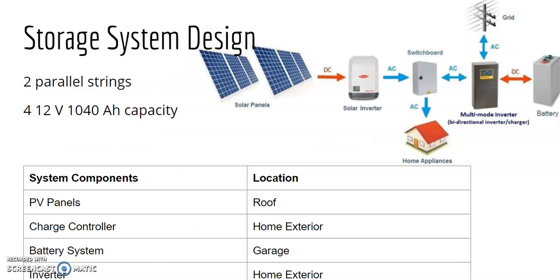For the system design, the storage system will consist of 2 strings of batteries, each string consisting of 4 12-volt 1040 amp-hour capacity batteries. Each component, as well as its location, is depicted on the table below. PV panels will be located on the roof, while the charge controller and inverter will be on the exterior of the home near the utility meter, and the storage system will be located in the garage. Our system will need to be sized to produce roughly 11,000 kilowatt hours of electricity to meet the client's 2020 demand.